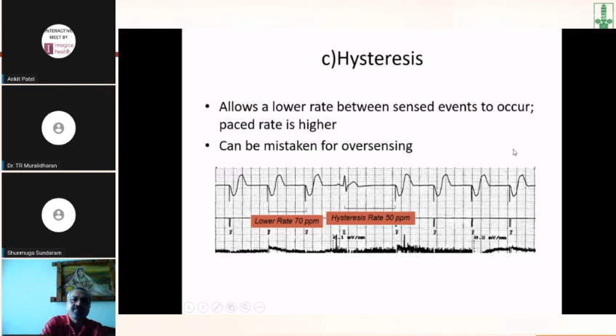So this can be mistaken for oversensing. We can see on the fourth complex there's an intrinsic beat. It is not oversensed, it's the hysteresis feature of the pacemaker which has been switched on. So whenever the heart rate drops to 50 or less, only then does the pacemaker start functioning at night. In the daytime it may function at 70 beats per minute. Next.